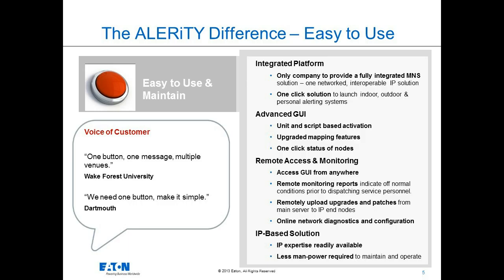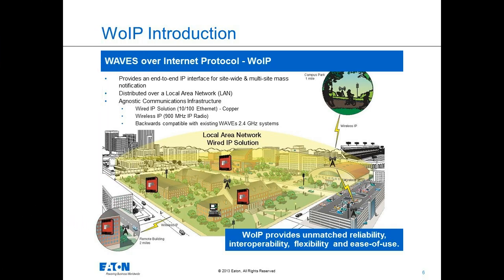So let's talk a little bit about why systems fail. I can't tell you how many times I'll go to a facility and nobody's been trained on their mass notification solution, what it is, depending on what it is. So in New York State, the state offers a free system, much like they have here in Connecticut, for any school that's in the state system to be able to alert people via text message or email. It's great. It takes them about 5 minutes to get a message out to anybody because they have to sit there and type it, send it, and by the time that gets distributed, it's 5 minutes after the fact.